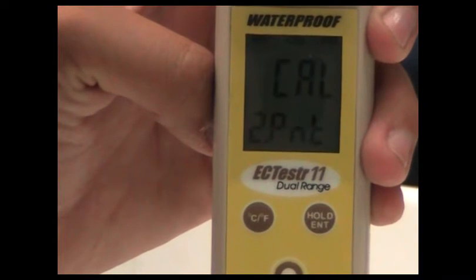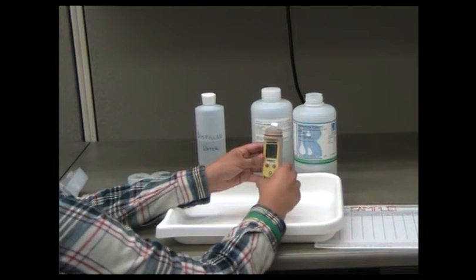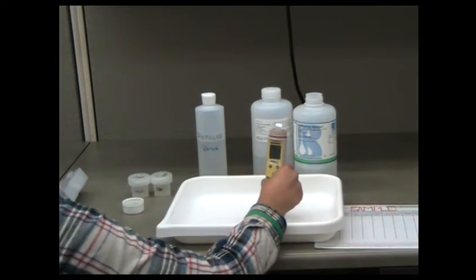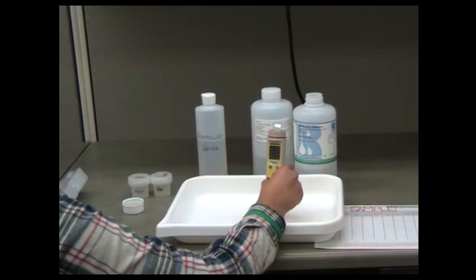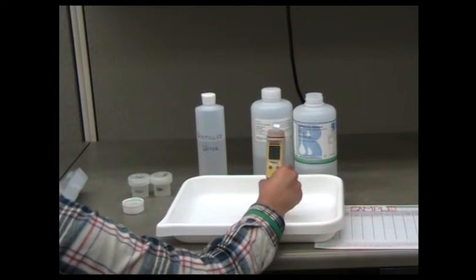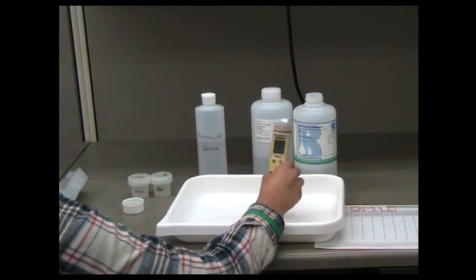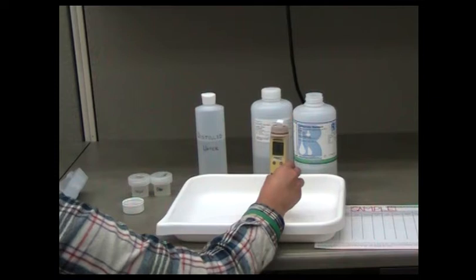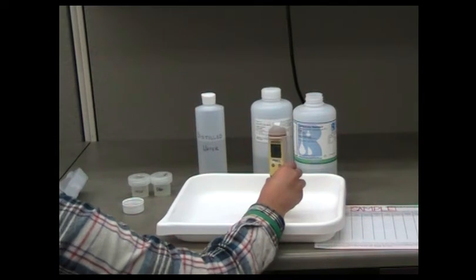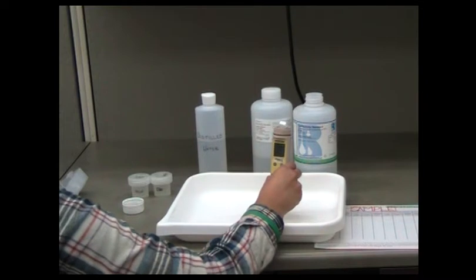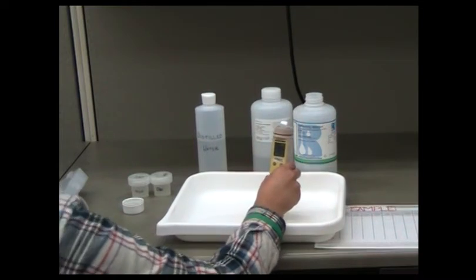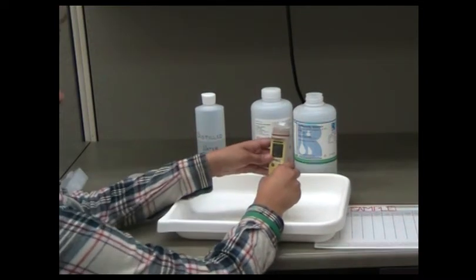2PNT should also flash on the screen. This means you have entered the two-point calibration process. The upper reading on the screen now displays the measured conductivity, while the lower reading displays the default uncalibrated conductivity reading. If the value displayed does not match the standard solution, use the increase or decrease buttons to correct the displayed value to that of the calibration standard solution.